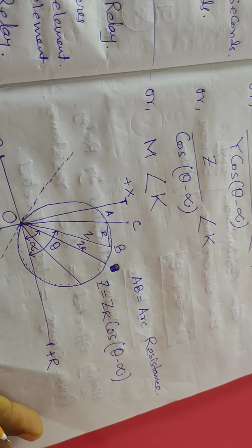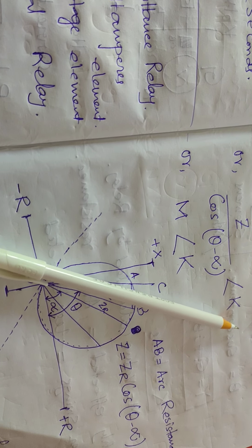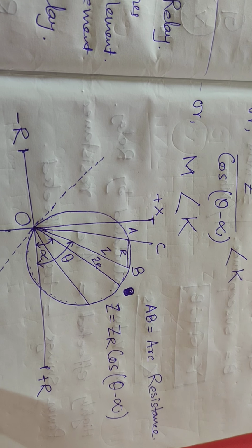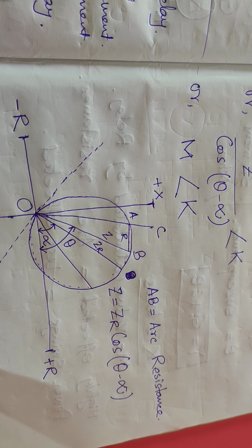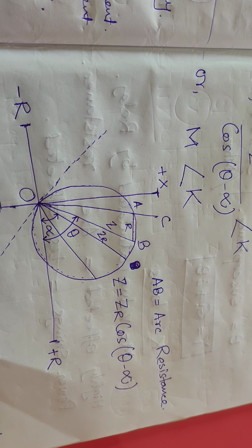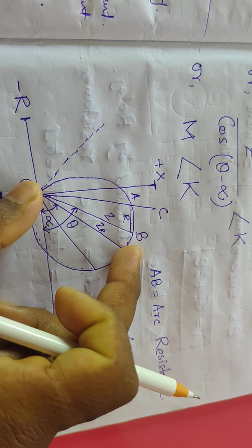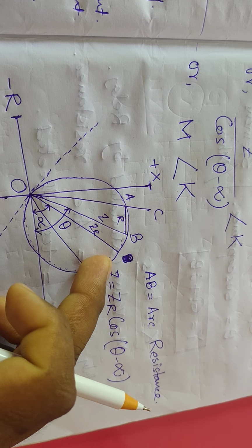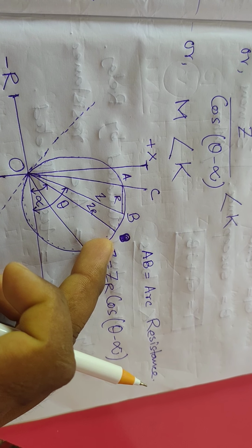The Mho relay operates in long transmission lines, and it is suitable for EHV and UHV heavily loaded transmission lines, as its threshold characteristic in the impedance plane is a circle passing through the origin, and its diameter is ZR. Because of this, the threshold characteristic is quite compact, enclosing the faulty area compactly, and hence there is a lesser chance of operating during the power swing.